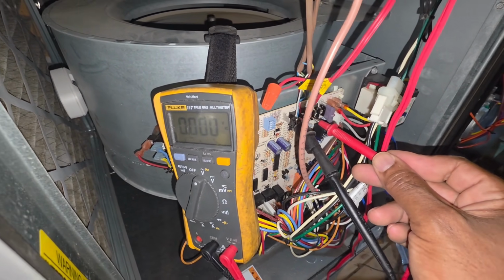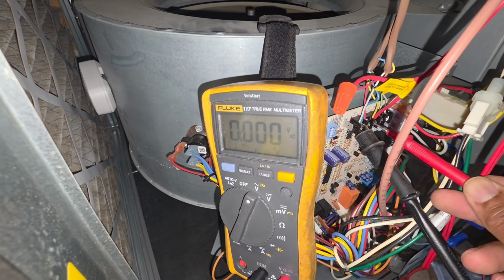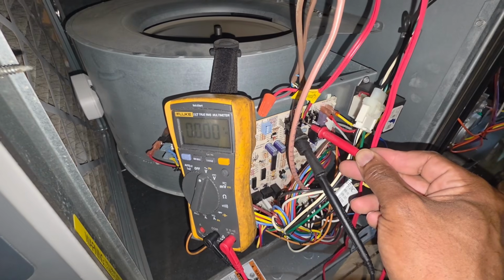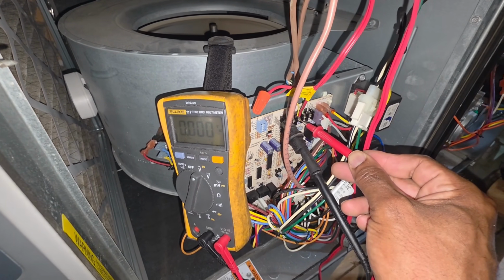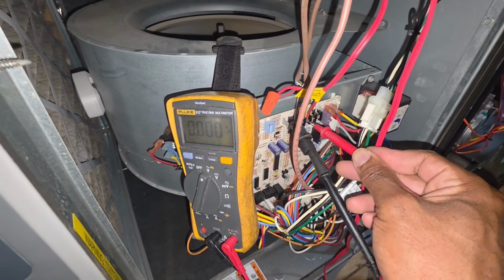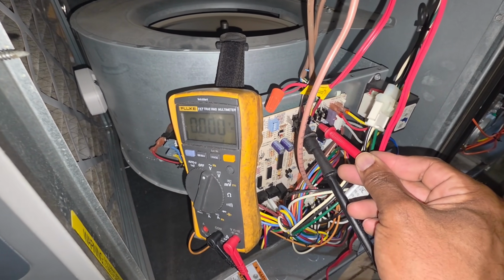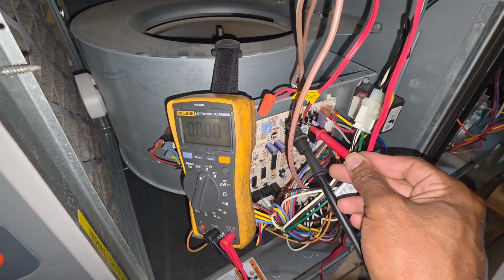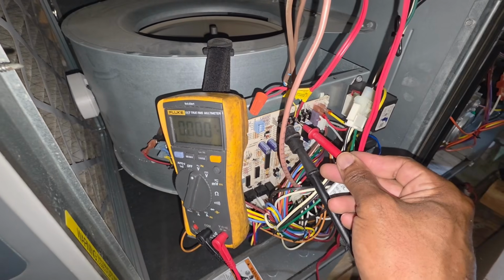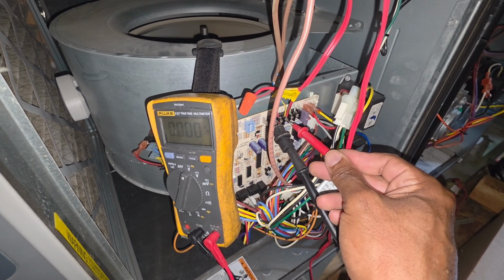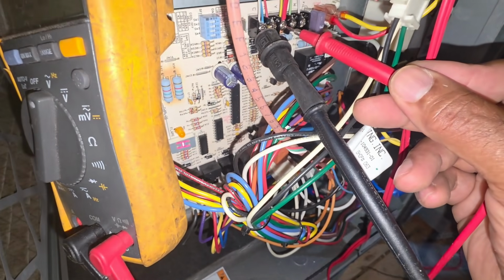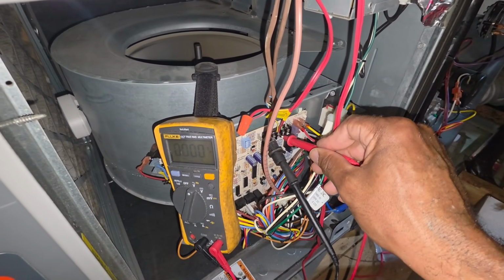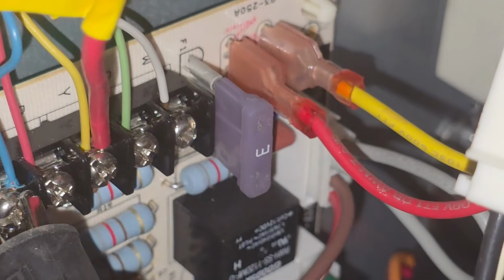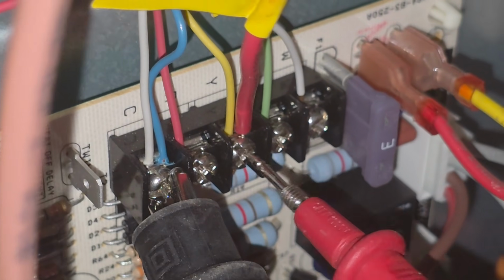Let's go to Y1. That's my cooling, my compressor right there. I should be getting 0. This is another part of troubleshooting. If I was getting 24 volts on my Y1, cooling and my compressor, on a standard natural gas furnace, if I was getting 24 right here, that means we need to be troubleshooting. We could have a pitted contactor inside the thermostat, or I've seen it where the compressor and the heating turn on at the same time. We don't want that. So you see right now that W on my control board, I'm just calling for heat. So if I was getting 24 volts right here on Y1, you see Y1, I am getting 0, which we should.